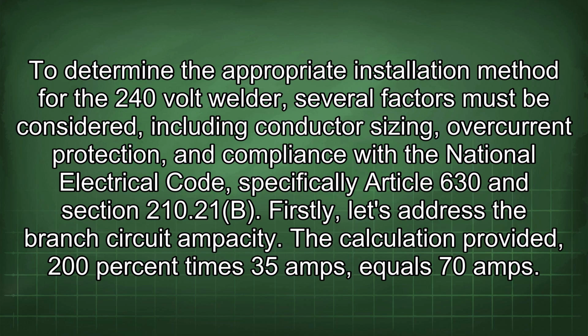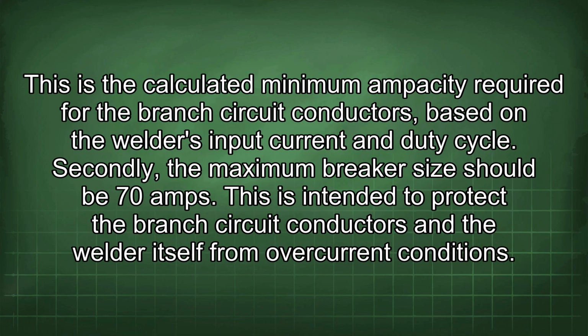The calculation provided 200% times 35 amps equals 70 amps. This is the calculated minimum ampacity required for the branch circuit conductors based on the welder's input current and duty cycle. Secondly, the maximum breaker size should be 70 amps. This is intended to protect the branch circuit conductors and the welder itself from overcurrent conditions.